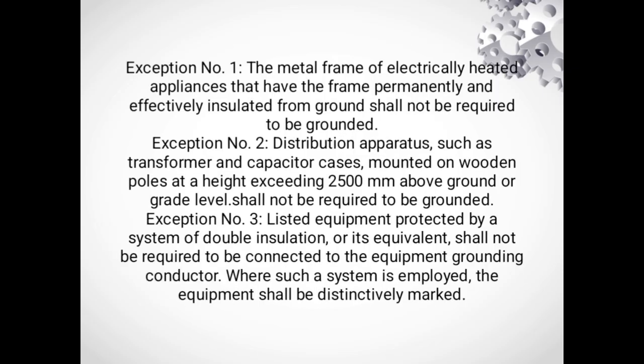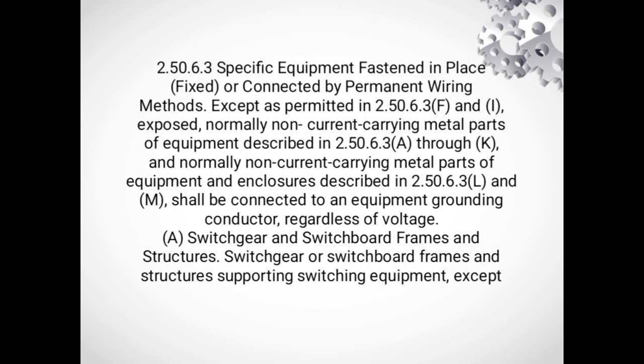Exception number 1. The metal frames of electrically heated appliances that have the frame permanently and effectively insulated from ground shall not be required to be grounded. Exception number 2. Distribution apparatus such as transformer and capacitor cases mounted on wooden poles at a height exceeding 2,500 mm above ground or grade level shall not be required to be grounded. Exception number 3. Listed equipment protected by a system of double insulation or its equivalent shall not be required to be connected to the equipment grounding conductor. Where such a system is employed, the equipment shall be distinctively marked.